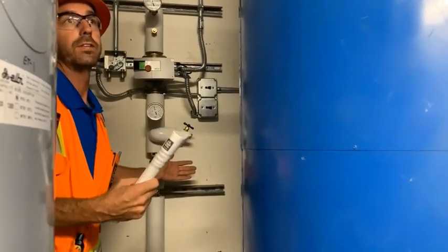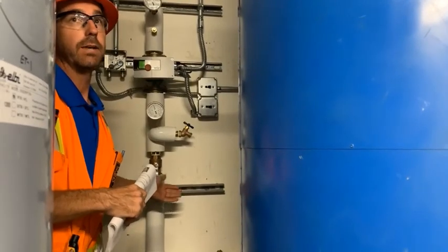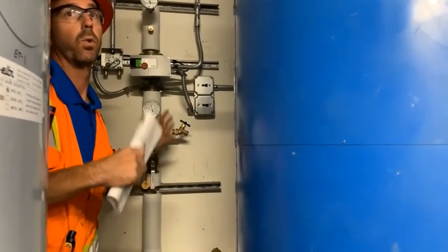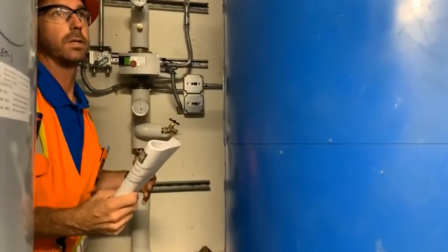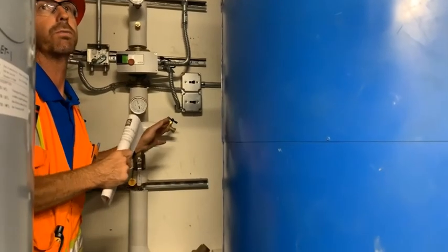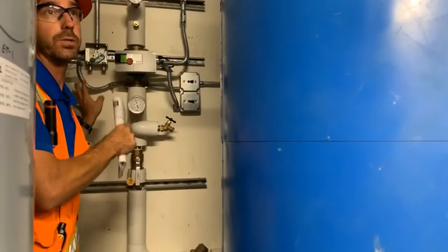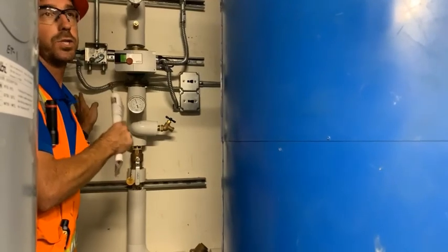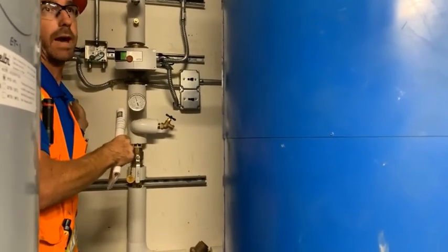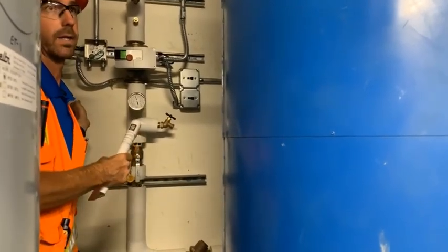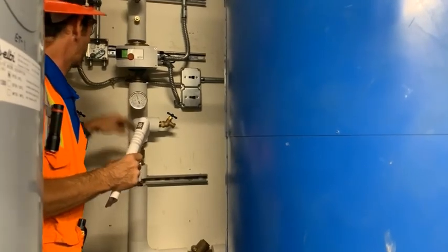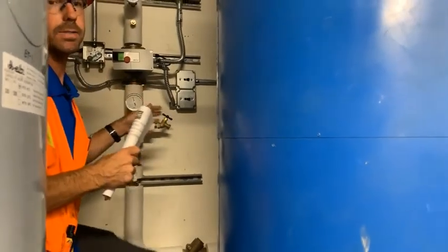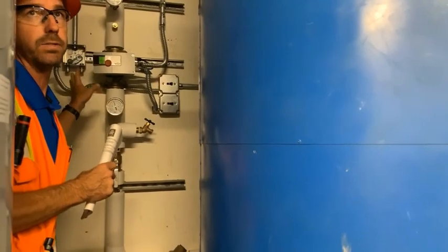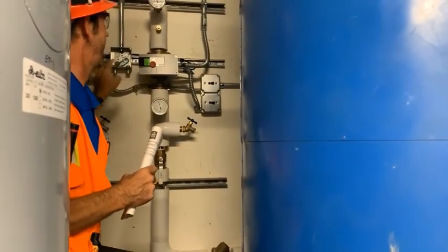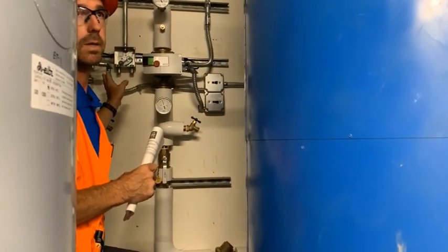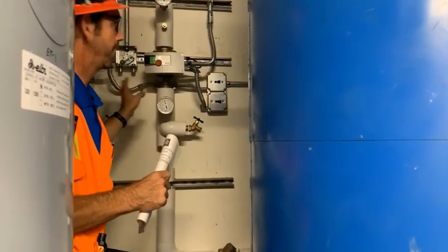Or if you know that someone drained the building, for whatever work or accident or purpose, you have to come here. If you know they are doing that work, make sure you shut off these pumps, okay? Because if you shut off the water out to the building and these are running, they'll cavitate and they'll burn up. Exactly. Okay, so if you're doing any work on the domestic, remember this is domestic hot water return pumps, make sure you shut off power to the pumps first, okay? Very, very first thing you do. Then start isolating.